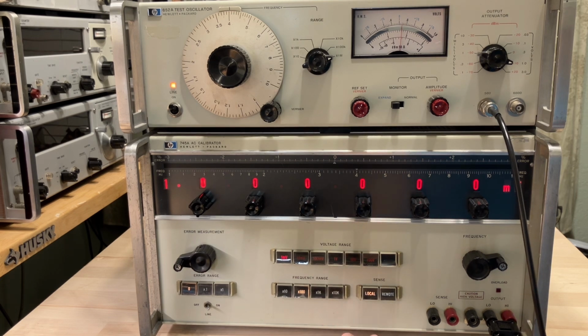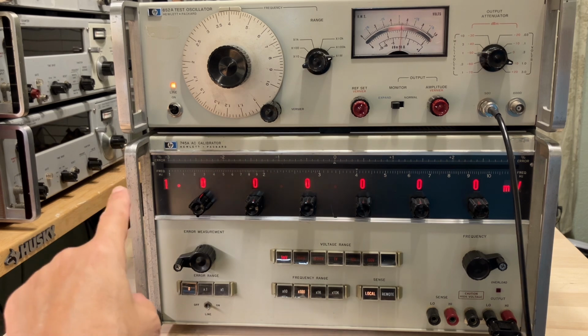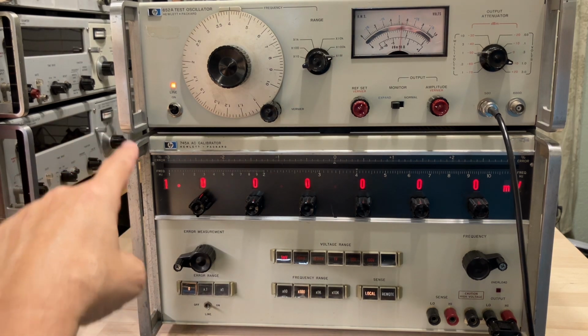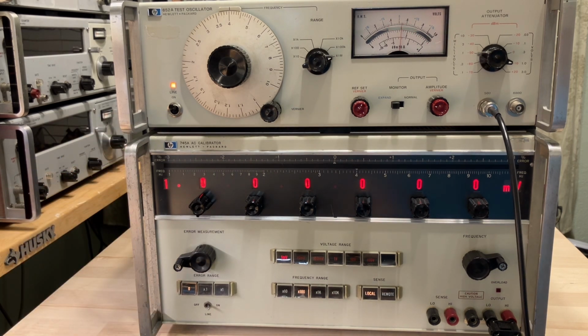On the bottom, we have the 740 HP 745A AC calibrator. It goes from 1 millivolt up to 100 volts with an external 1000 volt amplifier. There's a times 10 amplifier that you can add to it to calibrate above 100 volts up to 1000. I have the amplifier, it's behind it over here. You can't see it, but it's back over there, but it's not working currently. I have to do a repair on that amplifier.